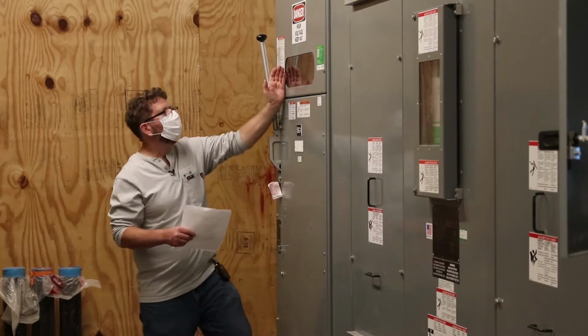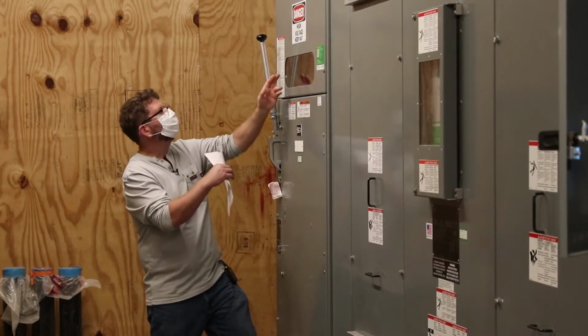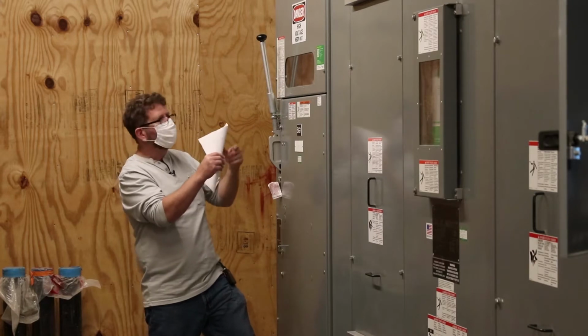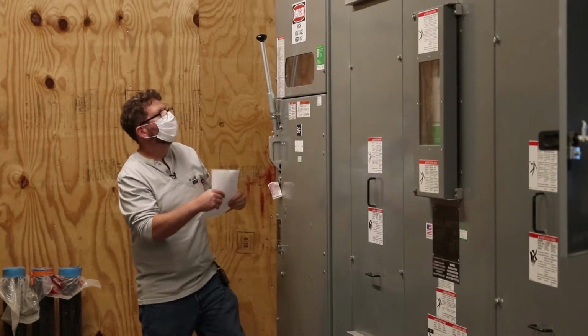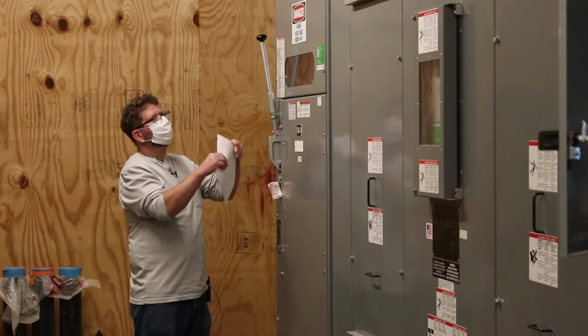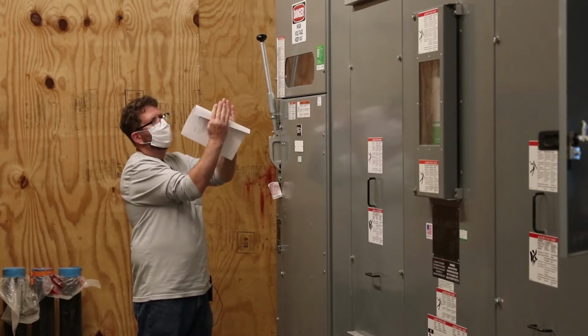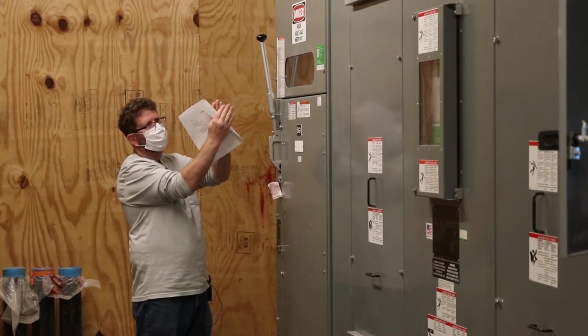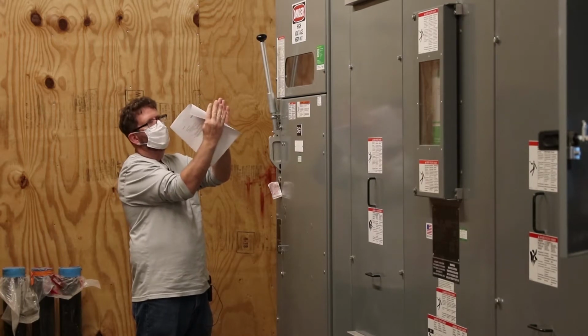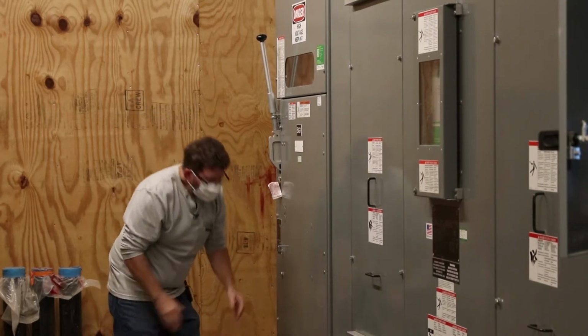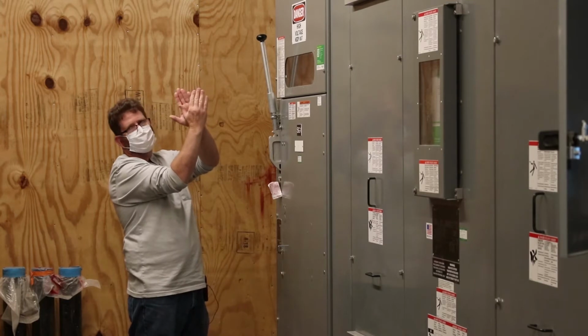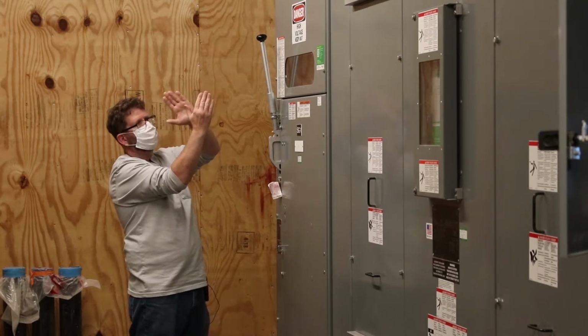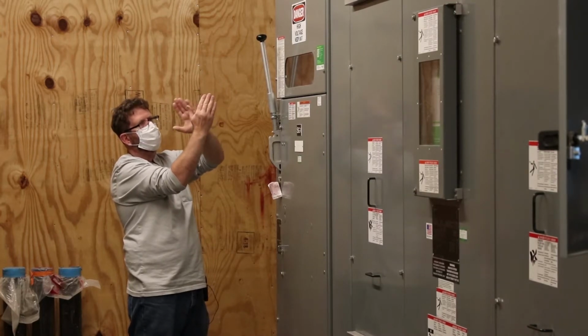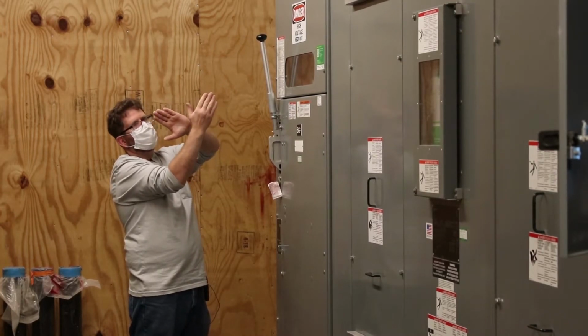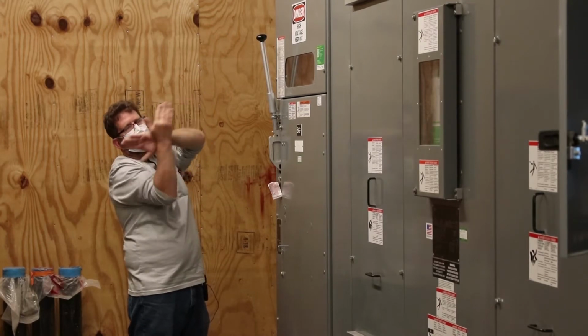When the switch blades open, you have the main blades, and to the right of those you have the arc tips. The arc tips are in the white housing. Those are the arc chutes. As the blades open, the arc tip is stuck in the arc chute, and it's on a spring, so as the blade comes open, the arc tip's going to stay in the arc chute. Once the movable blade is free of the stationary assembly, then the arc tip will pivot down and come out.